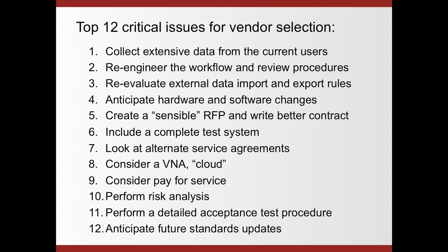It is relatively easy at that time to include it, because from a vendor perspective it's just another license of their database or archive manager and maybe a couple of licenses of their viewing station. So for them it's relatively little cost to throw it in, so to speak. And the hardware also: if you think about storing the data for maybe a couple of days, a relatively small computer system can do that for you. So include the test system up front, so you can have a potential short-term backup and also a switchover system, and it gives you a platform for any major modifications and changes.